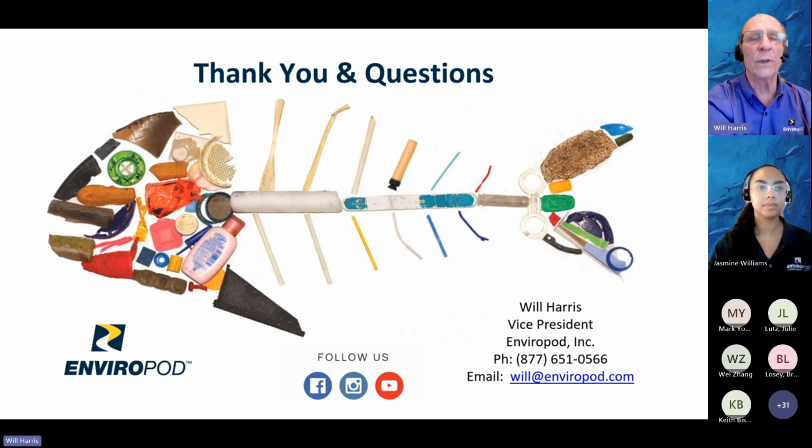And what we've seen working with our clients is that a lot of customers will start out maintaining them after major storm events, or on average twice a year, once in the spring and once in the fall. Certain drainage areas may be accumulating more trash and debris. You may have to maintain those drainage areas more often, whereas there might be drainage areas where you're not generating much trash and debris at all. Those might be once a year to once every 2 years we have to go out and maintain them.